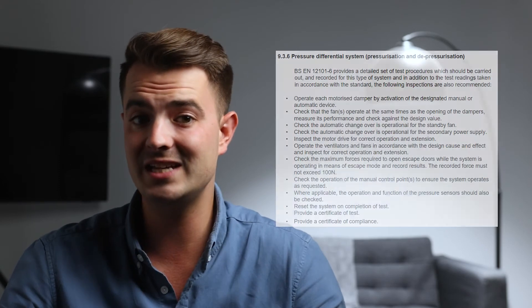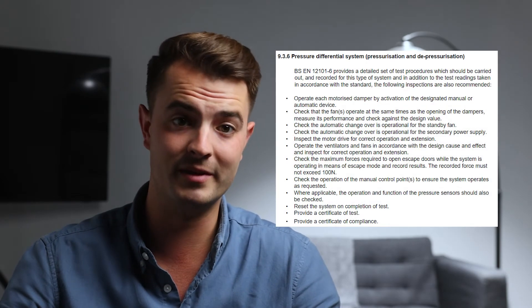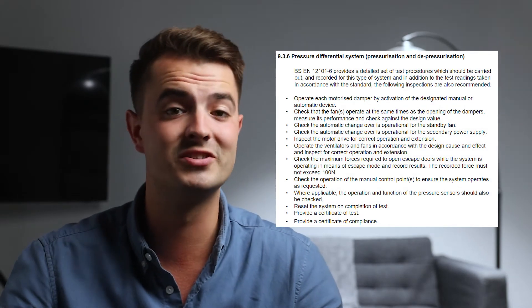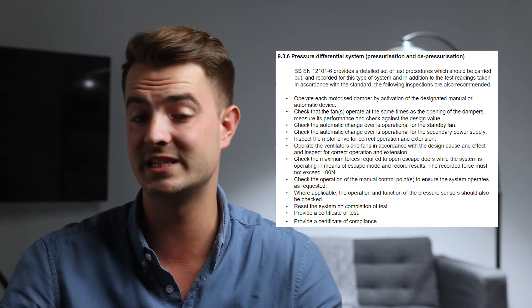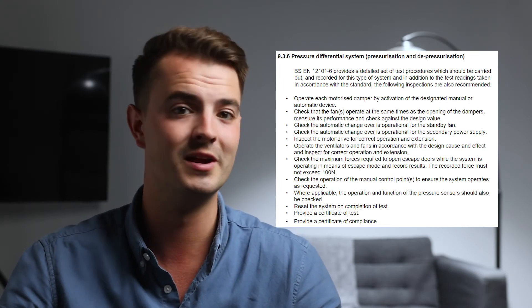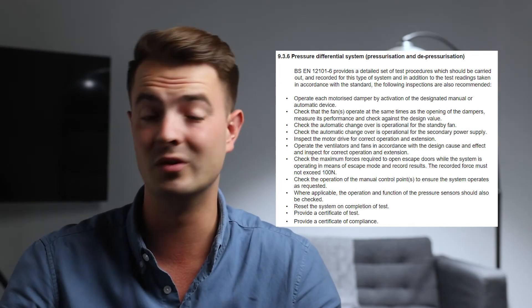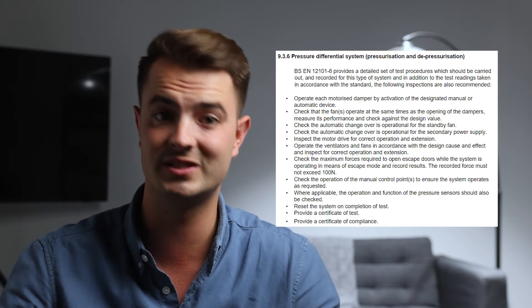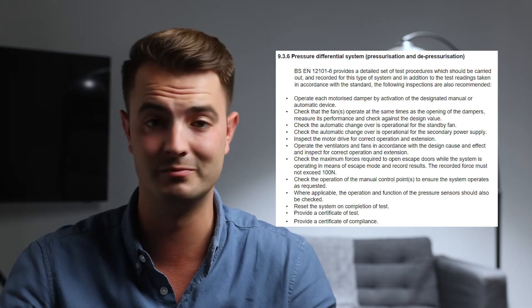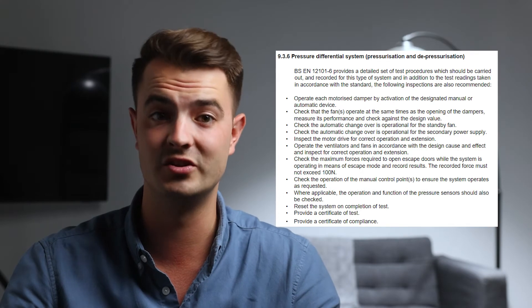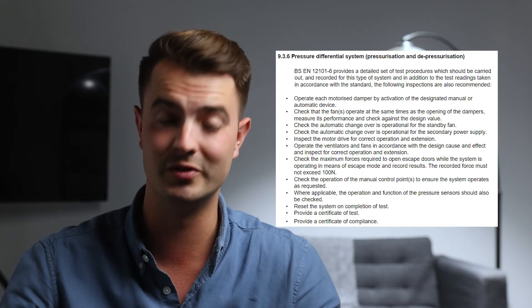The SCA guide also adds some additional recommendations. Lots of these recommendations are similar to procedures that would be carried out for the testing of all other smoke ventilation systems — for example, checking that all dampers work, checking automatic changeovers operate for standby fans and power supplies, etc. The full list can be found in section 9.3.6 of the SCA guide.